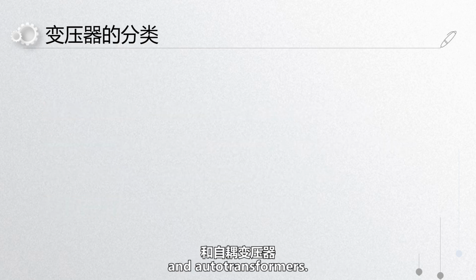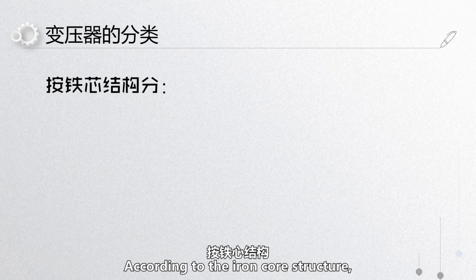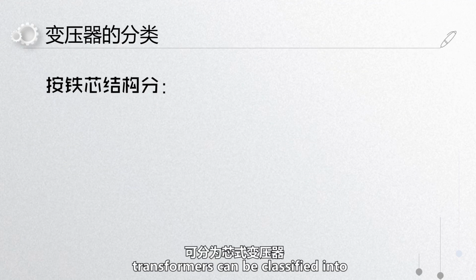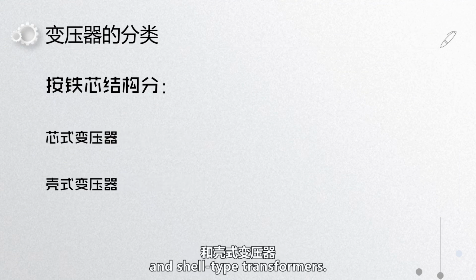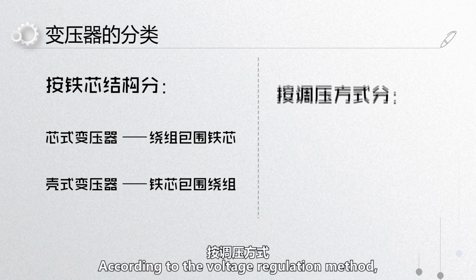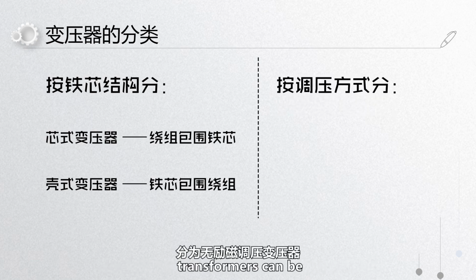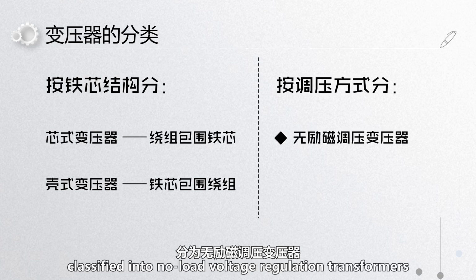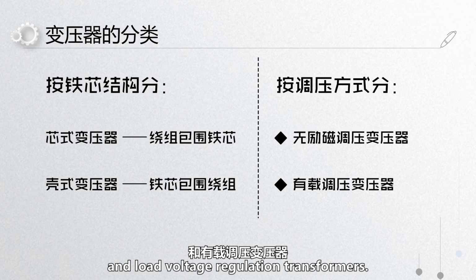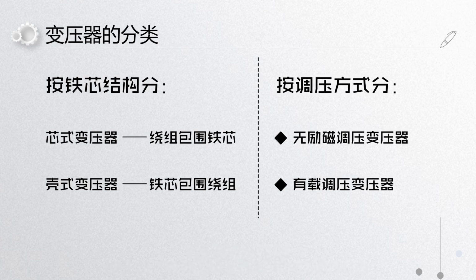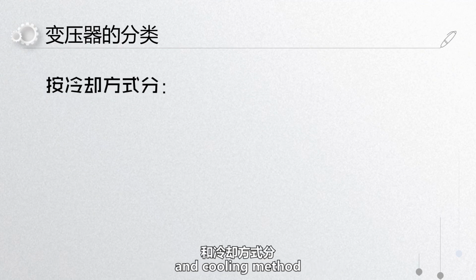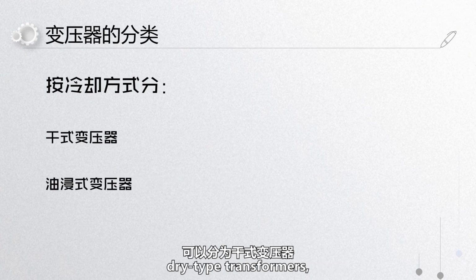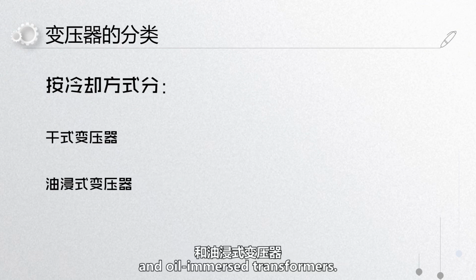and auto transformers. According to the iron core structure, transformers can be classified into core-type transformers and shell-type transformers. In core-type transformers, the windings surround the iron core, while in shell-type transformers, the iron core surrounds the winding. According to the voltage regulation method, transformers can be classified into no-load voltage regulation transformers and load voltage regulation transformers. According to the cooling medium and cooling method, transformers can be classified into dry-type transformers and oil-immersed transformers.